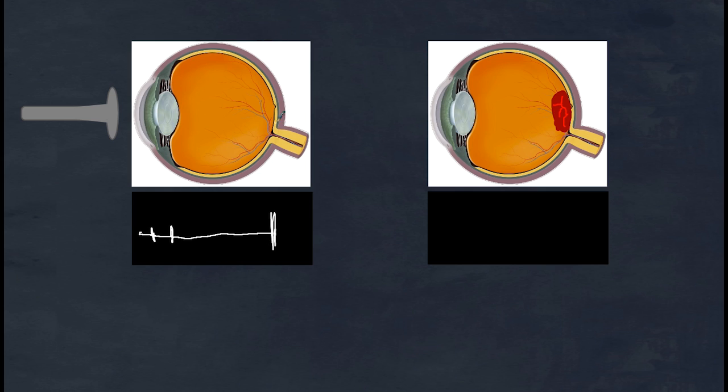And of course, here we hit the back of the retina and of course the other parts of the eye, namely the choroid and the sclera, and they're a lot denser than the lens, and so therefore we're going to get a higher peak. But clearly, all of a sudden, we have the ability to measure the size of the lens, okay, and of course also the distance between the lens and the back of the retina over here.